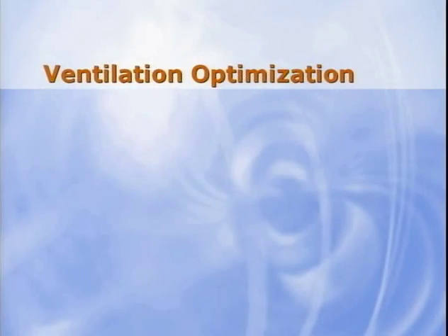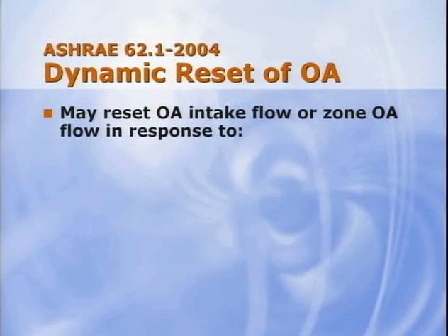Next topic, ventilation optimization. In a typical rooftop VAV system, the rooftop unit delivers fresh outdoor air to several individually controlled zones. Now, as we mentioned in our broadcast last November, the 2004 version of ASHRAE Standard 62 now explicitly permits dynamic reset of outdoor airflow as operating conditions change. The standard lists some examples of dynamic reset, including these two.